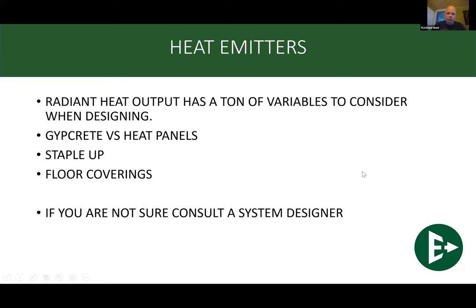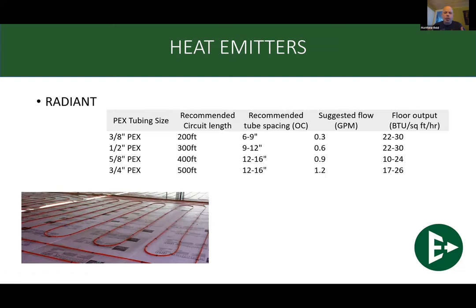Now, there are ways that you can increase the BTU output of radiant tubing. The aluminum panels, for example, work like crazy to bump up that heat output. It turns a standard PEX line into a big heat emitter. So imagine a bunch of aluminum rads in your floor, just underneath the subfloor. You can get a ton more BTUs out of that. Also, you can bump up the insulation beneath that PEX, because one thing I can't stress enough is that heat, by no means, rises at all. I don't care what your grade 9 science teacher told you, it does not rise. Heat transfers to cold. Now, it's true, warm air rises and warm water rises, absolutely.